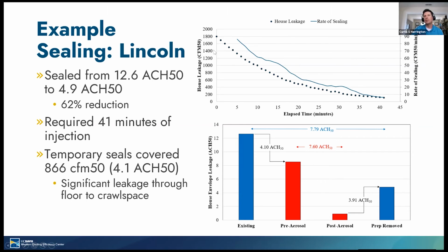So we're sealing 90% of the leakage that's available. That's about as good as we can expect from this process. This line shows the rate of sealing, shown on the secondary y-axis. At the beginning of the process, we're sealing about 85 CFM50 every minute, and it drops down as the process continues until the building is no longer sealing, at about 5 CFM50 per minute.